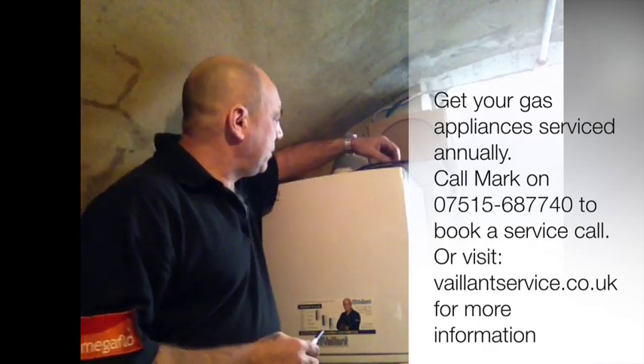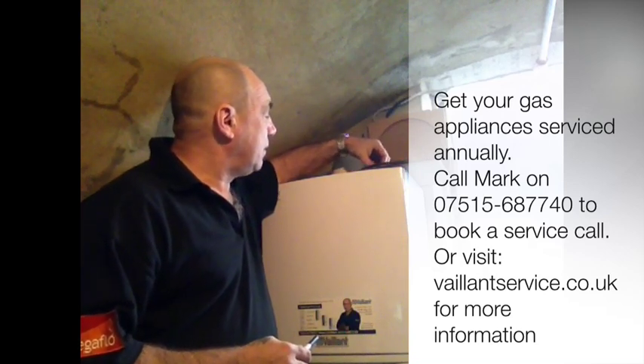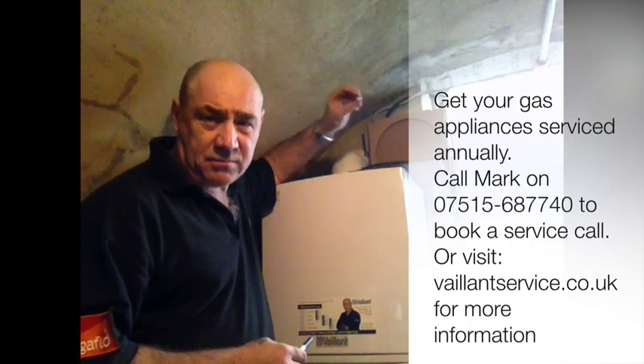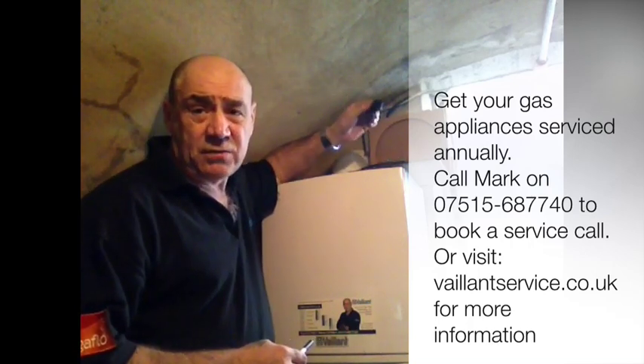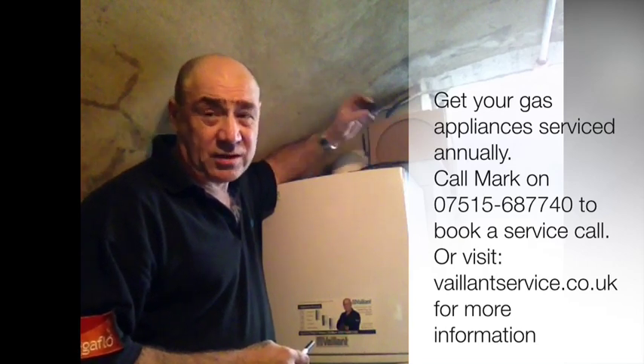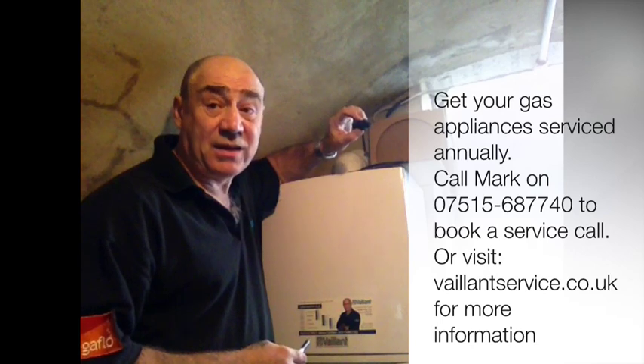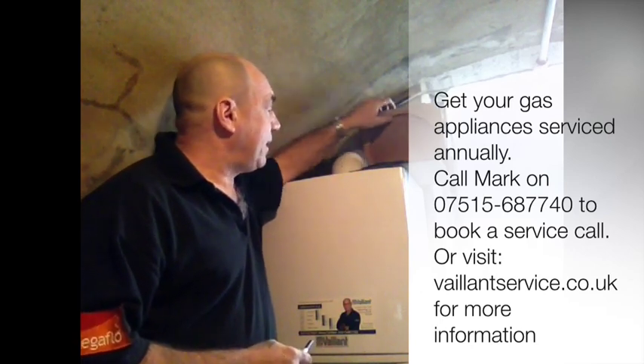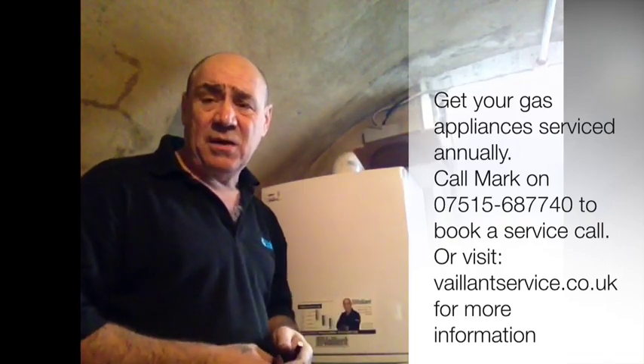And if you look up here, you'll see the old seal, the old bolts for the combustion chamber which haven't got nylon threads, so you can see that those are the wrong ones. And also the old sensor which I've changed just as a bit of Christmas insurance really. Don't like these very much, always change them, cures a lot of problems without having to turn up and drive all the way through London. So there you go, I'll leave that there so that the customer can see what they've actually had done and the parts they paid for.